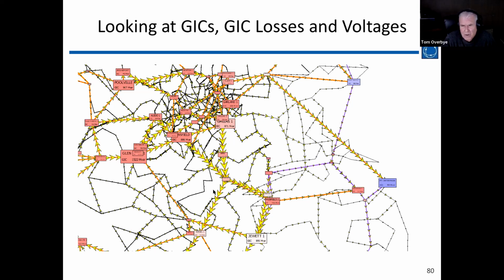I did mention on the slides that not all transformers are created equal—some are much better able to handle GICs from a heating point of view and also a reactive power consumption point of view. Those might be the transformers you want in service so they shunt the GICs to ground, because ultimately the GICs are induced in the high voltage transmission system and they're going to ground one way or another. The idea is we want to control how they go to ground.